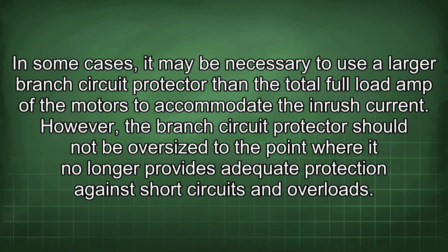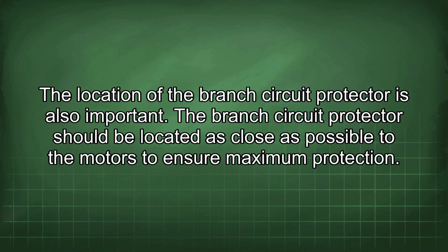In some cases, it may be necessary to use a larger branch circuit protector than the total full load amp of the motors to accommodate the inrush current. However, the branch circuit protector should not be oversized to the point where it no longer provides adequate protection against short circuits and overloads. The location of the branch circuit protector is also important.